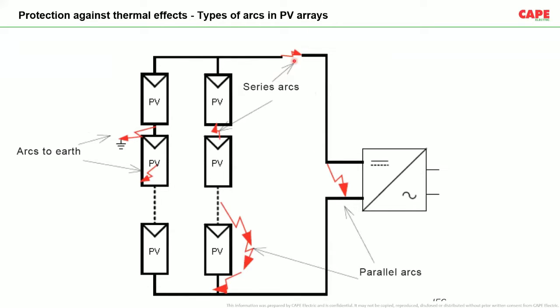The first one is the series arc, which means there is a loose contact in a terminal and there is a series arc. Arc to earth means there is an insulation failure and the wire is touching some metallic part. That means the double insulation itself has broken, and the conductive part is in touch with an exposed or extraneous conductive part. As a result, arc to earth is happening. There are two chances: one is arc from the wiring, and the next is arc within the PV module.